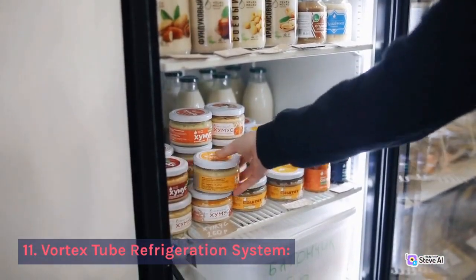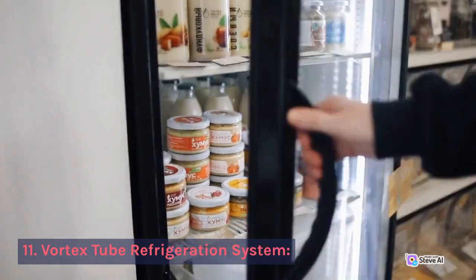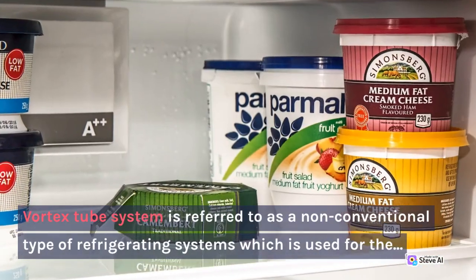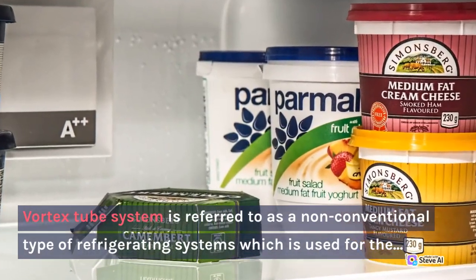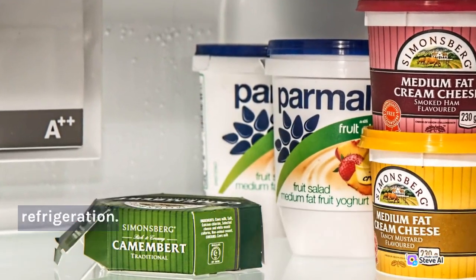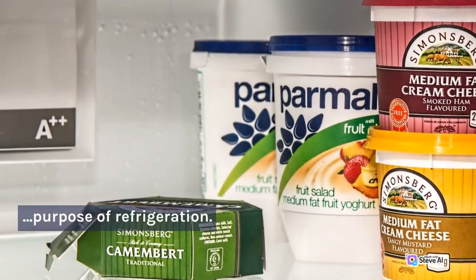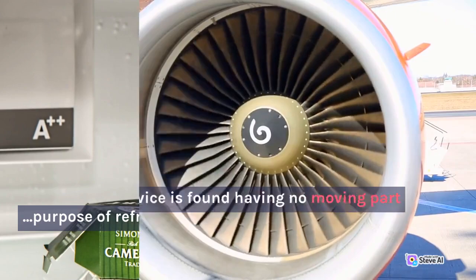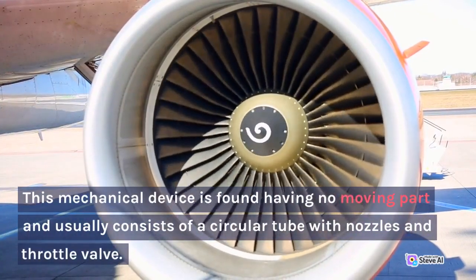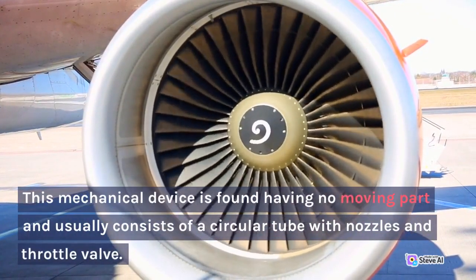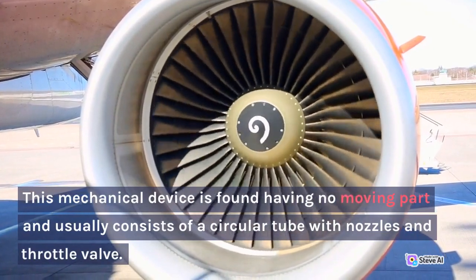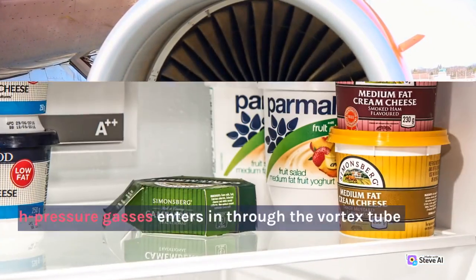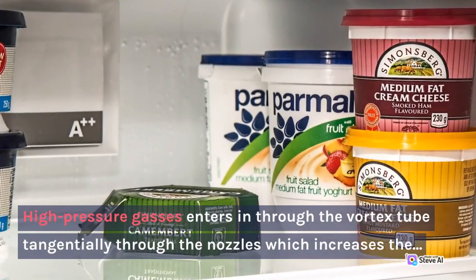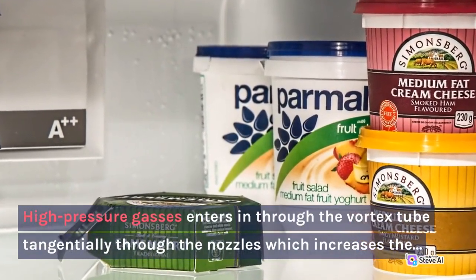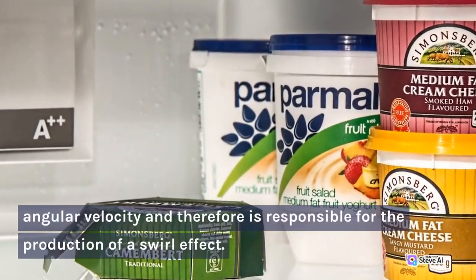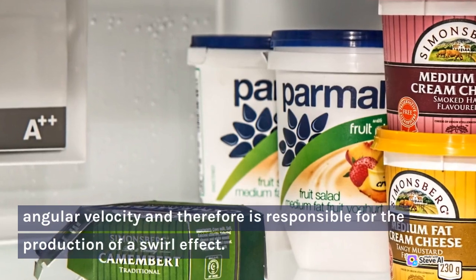11. Vortex tube refrigeration system. The vortex tube system is a non-conventional type of refrigerating system. This mechanical device has no moving parts and usually consists of a circular tube with nozzles and a throttle valve. High-pressure gas enters the vortex tube tangentially through the nozzles, which increases the angular velocity and is therefore responsible for the production of a swirl effect.